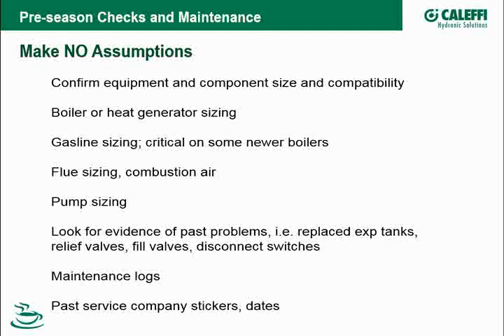You know, have you had problems with this since you've been here? Does it keep up, you know, when it's cold outside? Does it keep up with the heat load? Fuel costs, are they realistic? Is that what you think they should be doing? This is a good time to suggest improvements, you know, pump sizing or boiler changes or stuff like that.